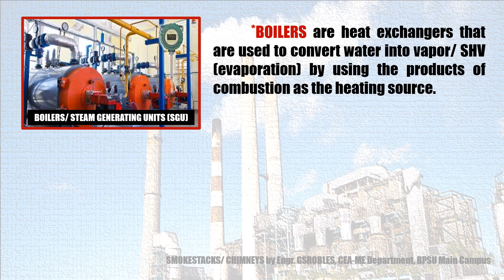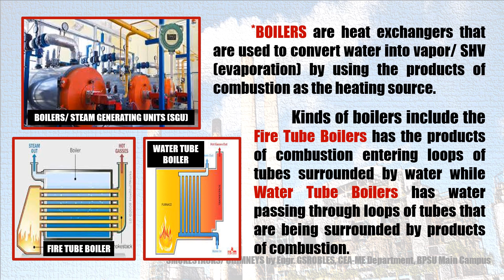The difference between the two is in where the water and products of combustion are located. In a fire tube boiler, the fire or products of combustion are inside loops of tubes surrounded by quantities of water. This is the complete opposite of the water tube boiler, where the water to be evaporated is located inside the loops of tubes, with the products of combustion or the fire itself encircling these tubes.